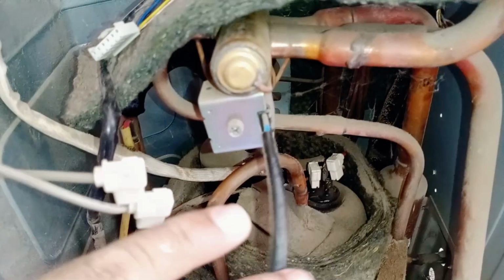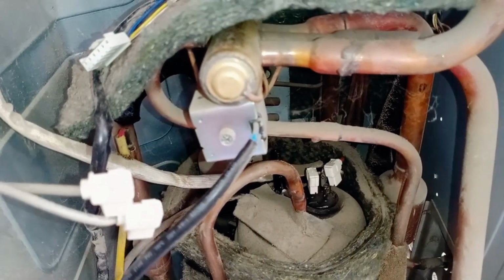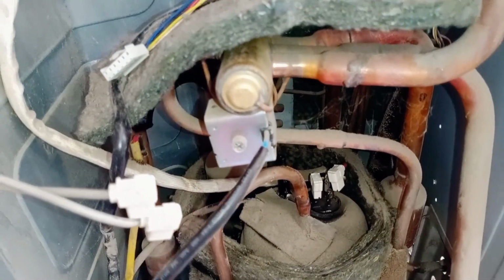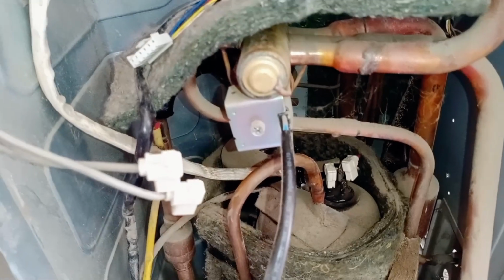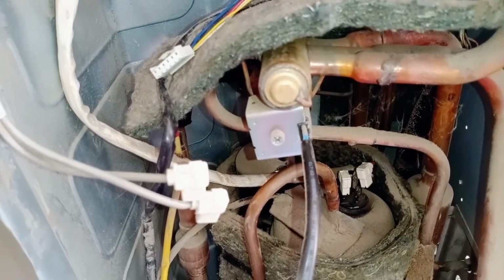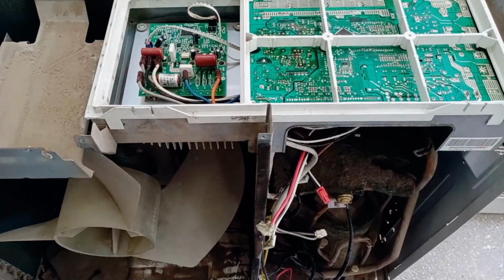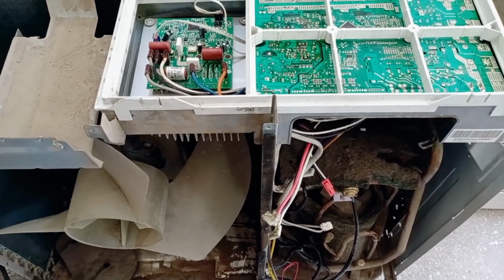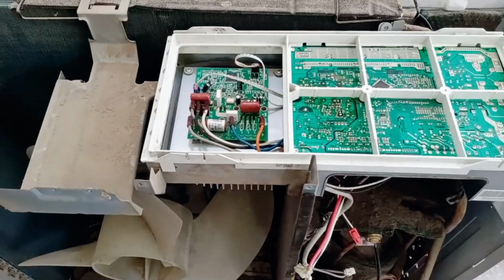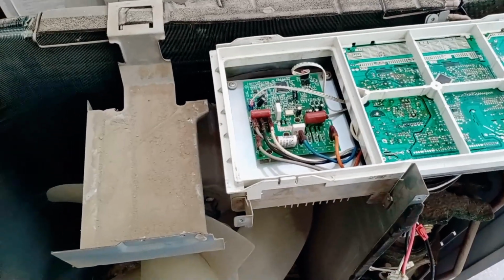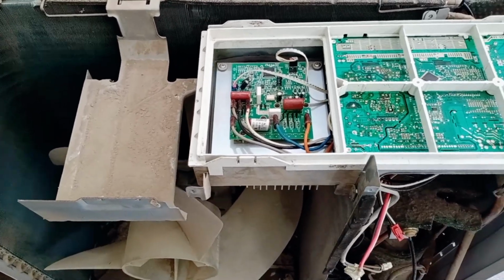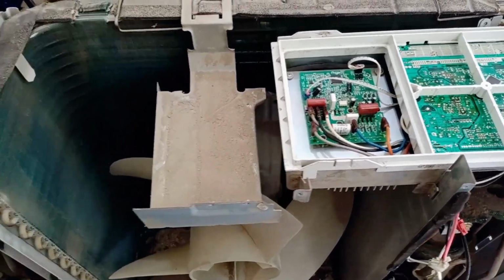If you repair or install a new circuit board without checking the compressor, it could cause the circuit board to fail again. This will lead to a loss of both your money and time. So, let me show you how to test the compressor and what its condition is. If the compressor is in this kind of state, do not install the circuit board on it, as the compressor will cause further damage to the circuit board.